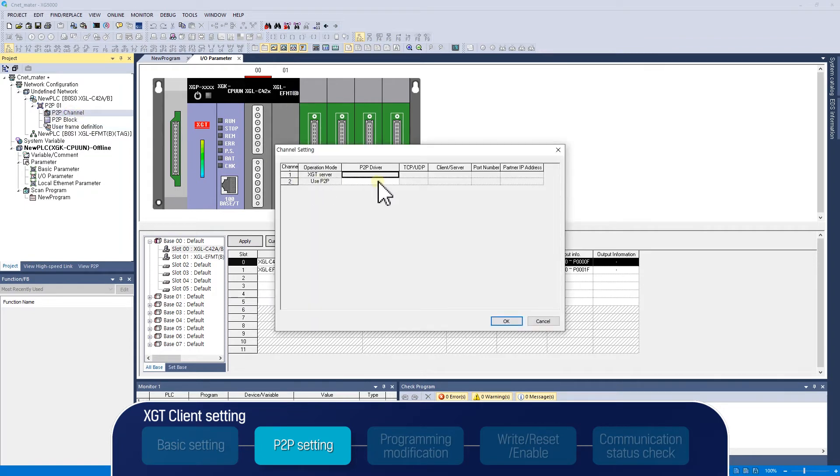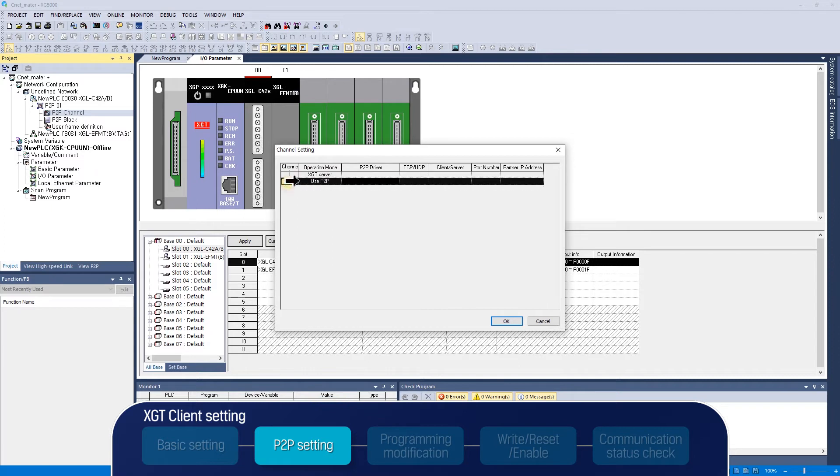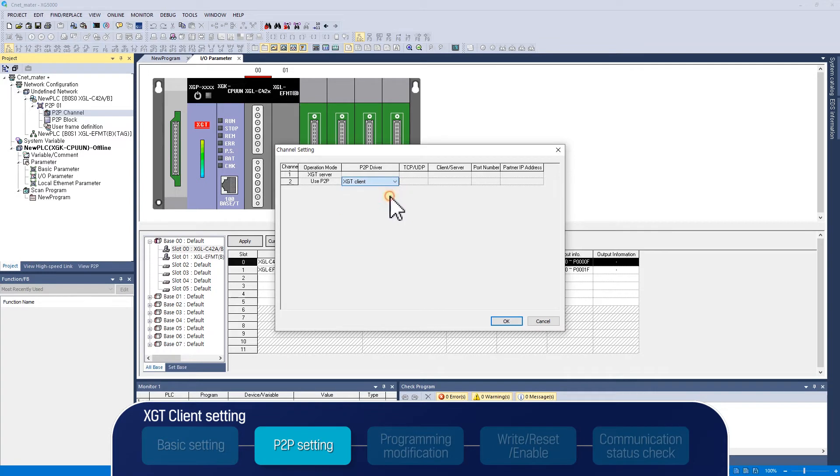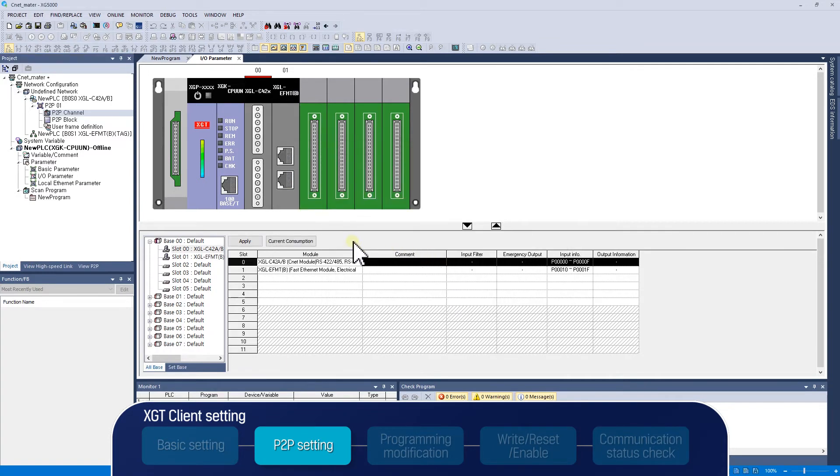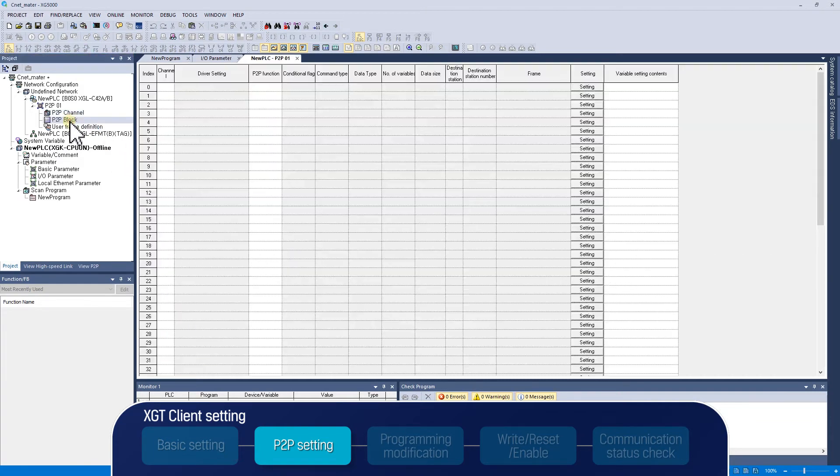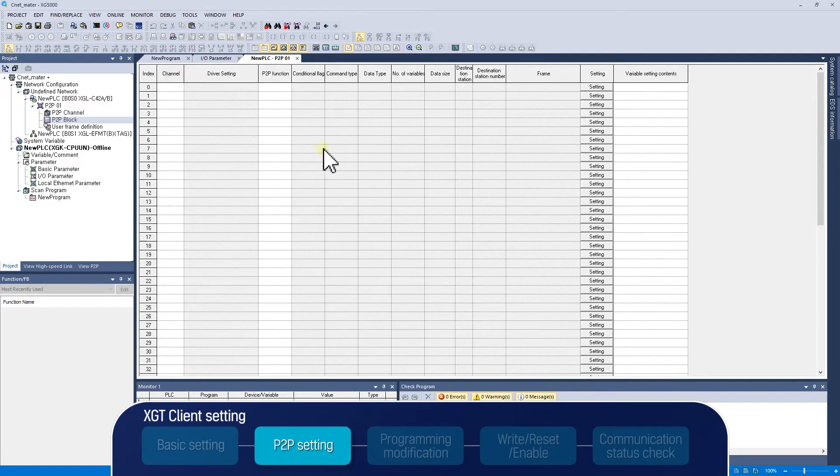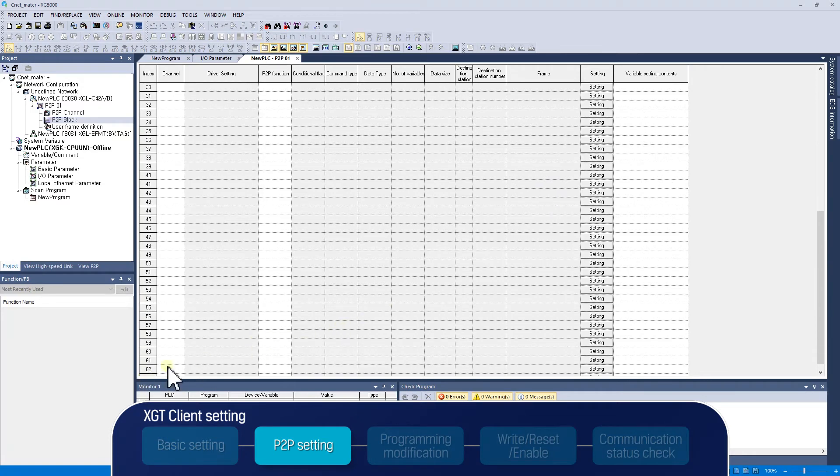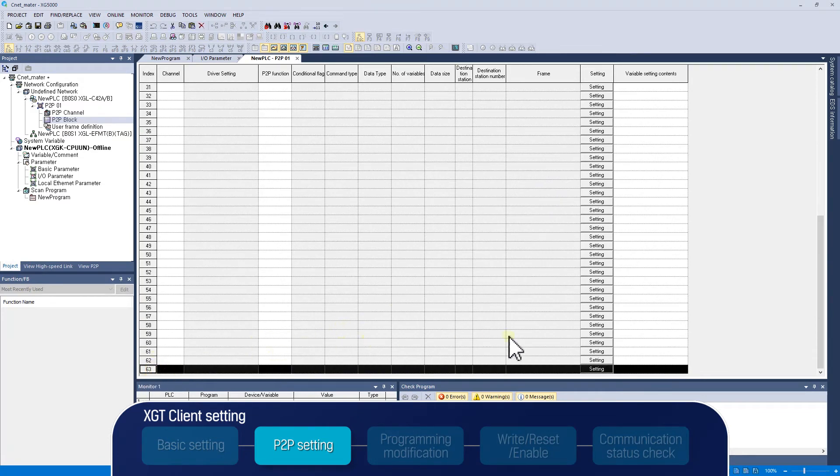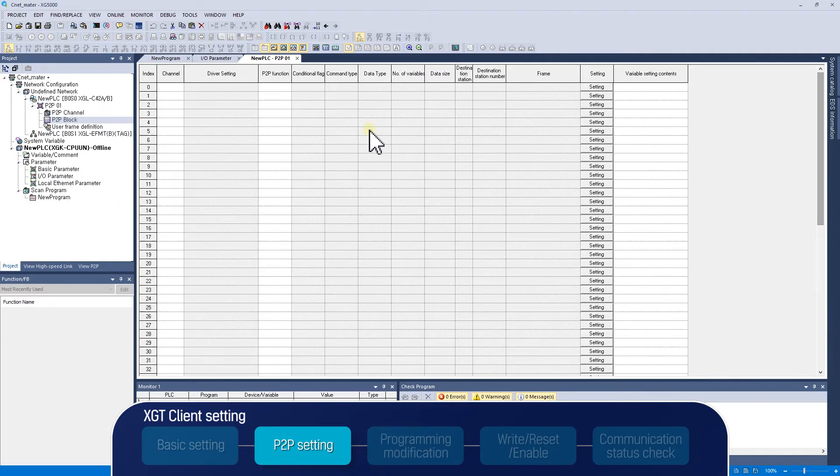Since RS422 of channel number 2 will be used in P2P channel tab, set P2P driver as XGT client. After P2P channel setting, move to P2P block setting. On the P2P block settings tab, sending receiving messages can be written in table format. You can write up to 64 indices per P2P. Each index contains one message. In this example, we will write one read request index and one write request index.